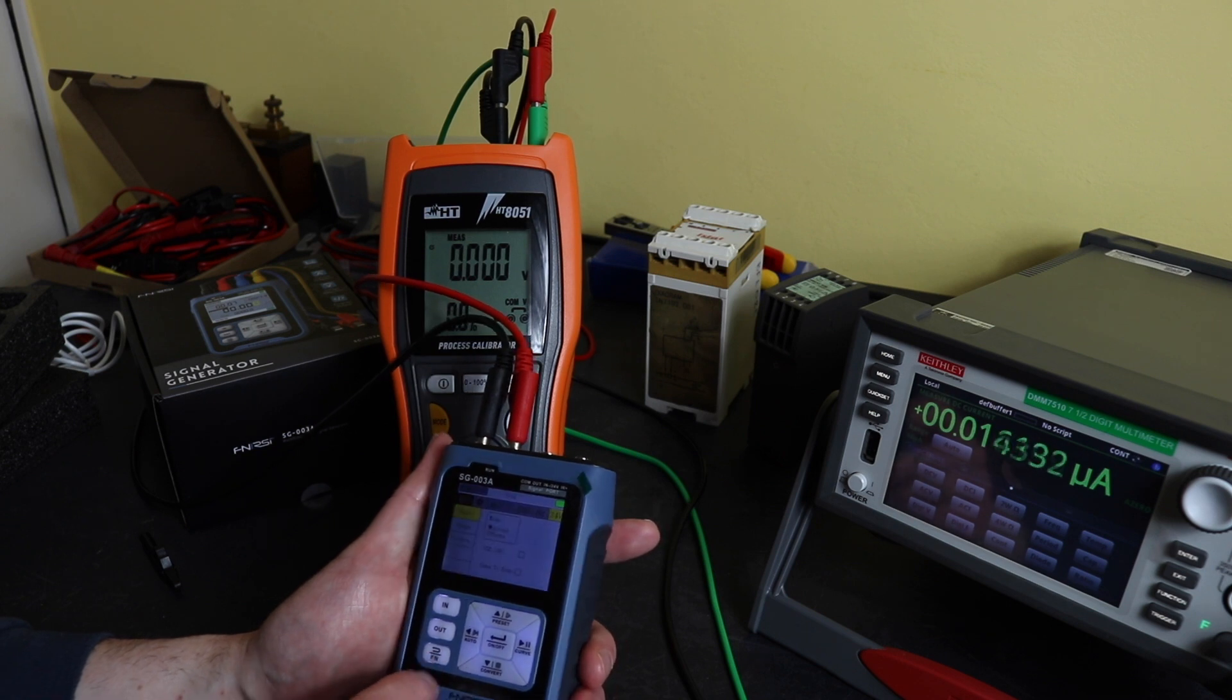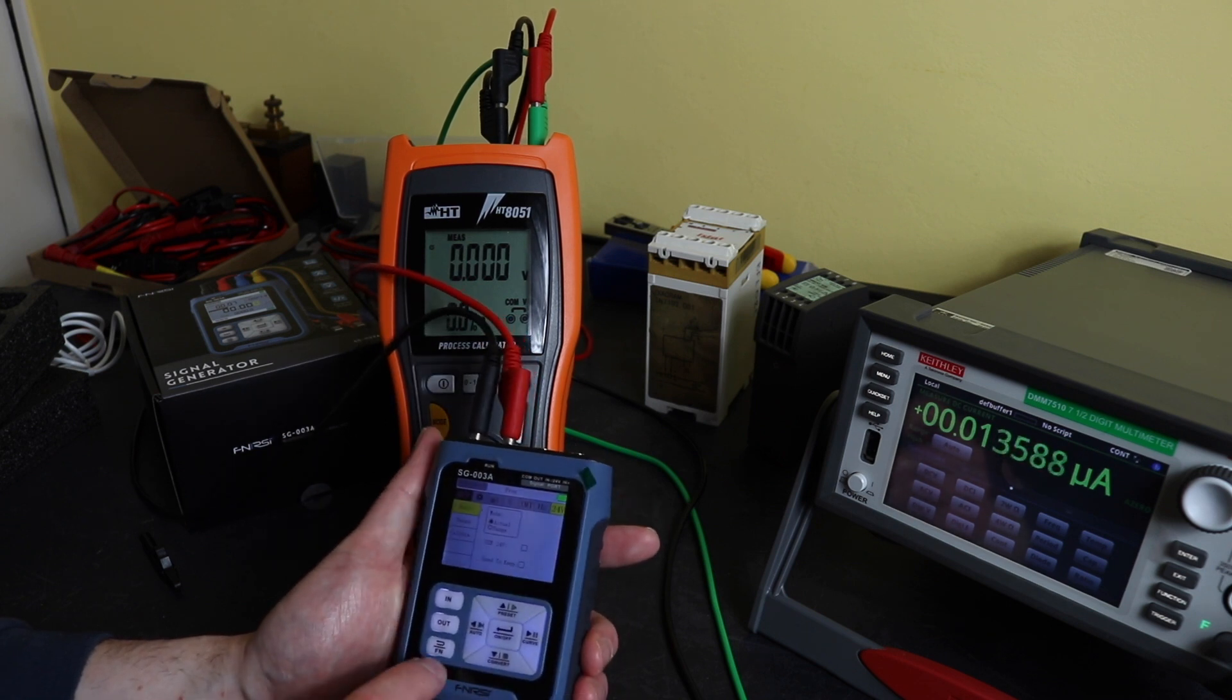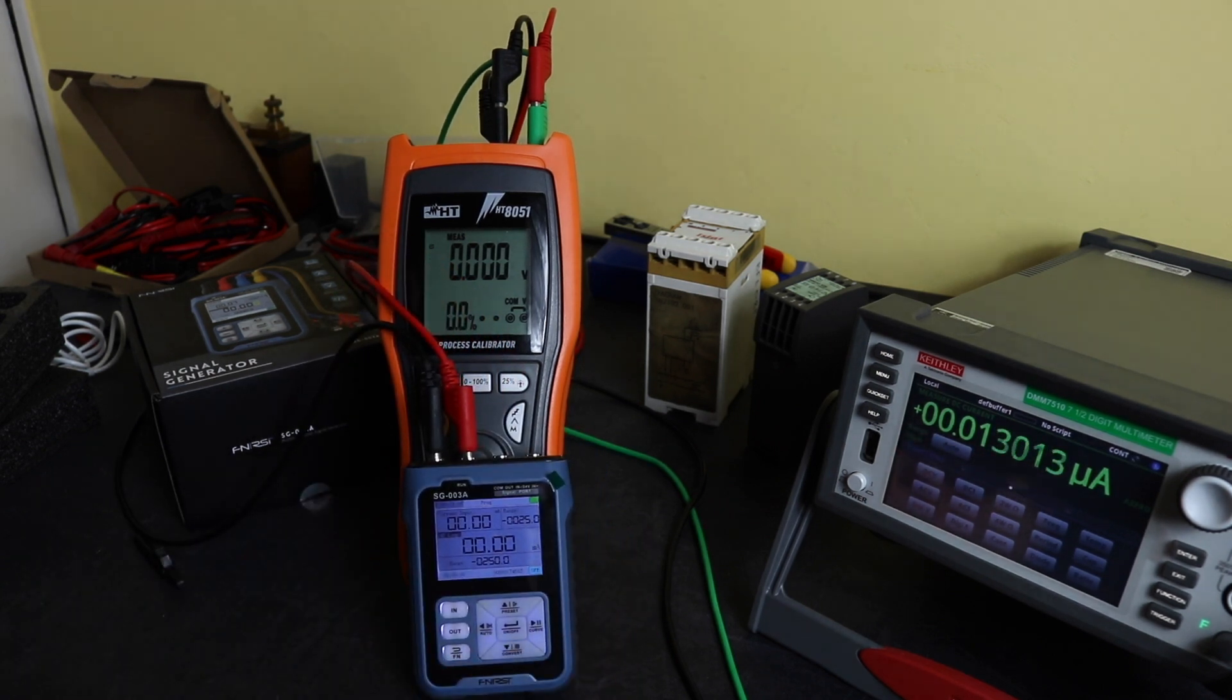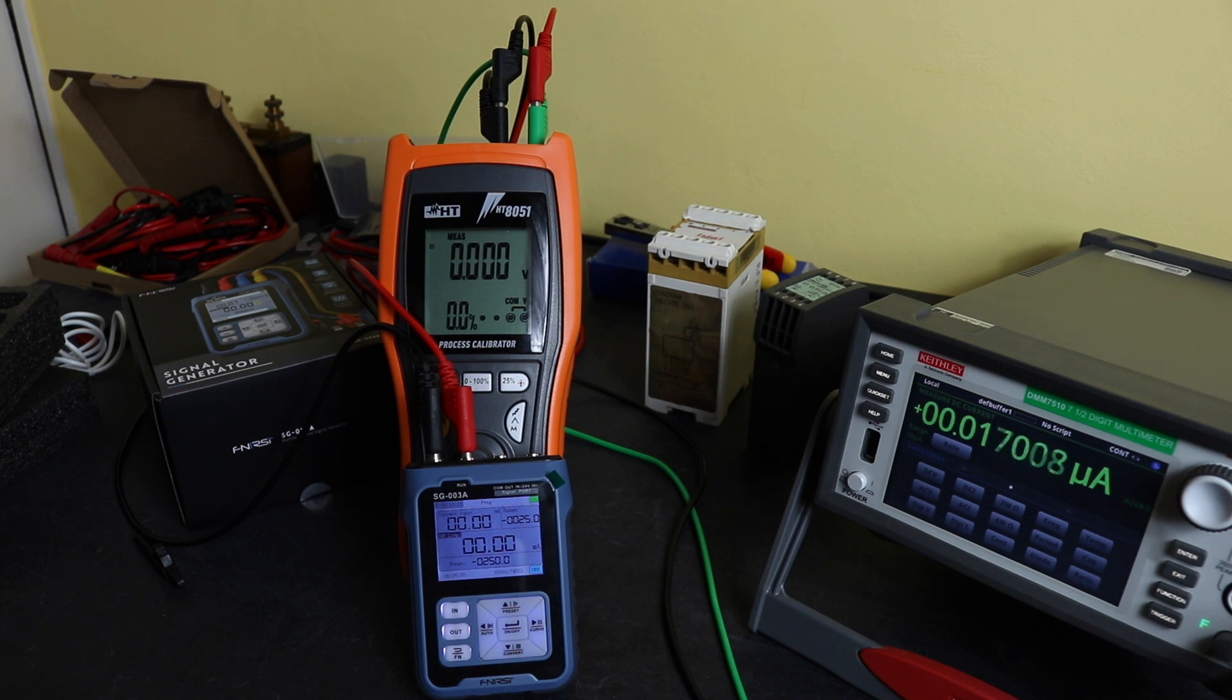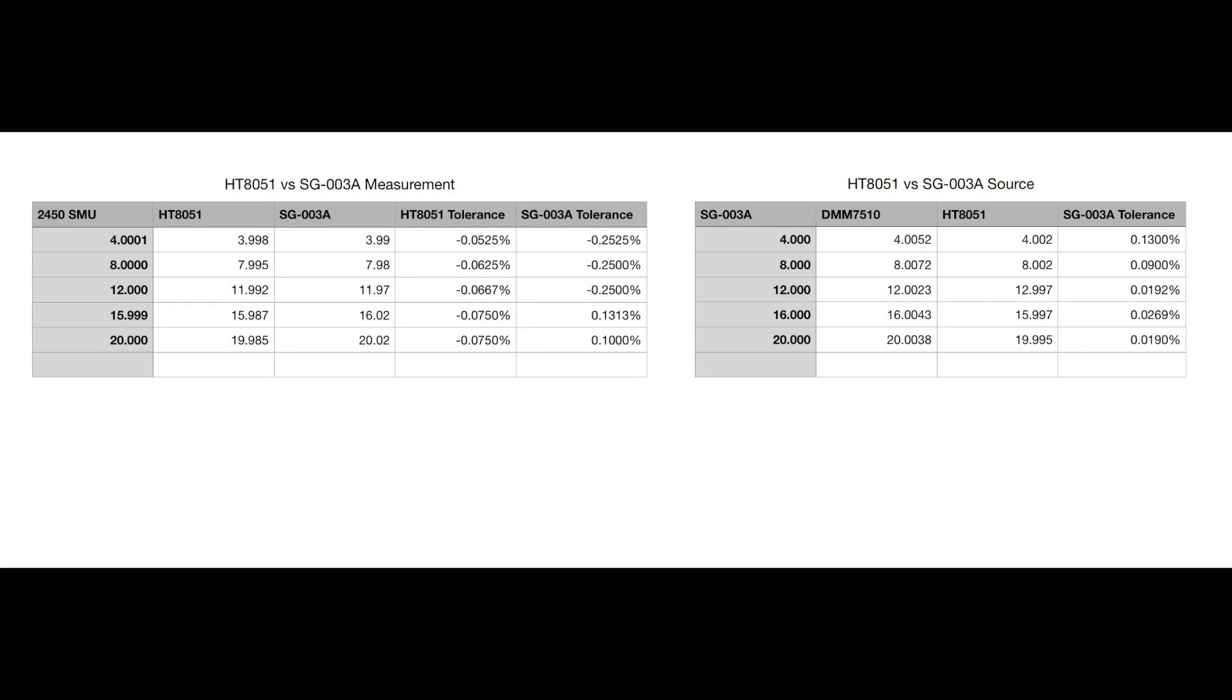I'll put the tables up now for the actual results of the measurements that I made. If you take a look across them, the unit is actually better at sourcing, more accurate at sourcing the output current rather than the measuring of it. We did see that whilst you were measuring it, you did actually lose one of the decimal points. There's only two decimal points for the measurement instead of the three that you see on the HT8051. There's room for improvement on the measurement function, but sourcing it does seem to be pretty good.